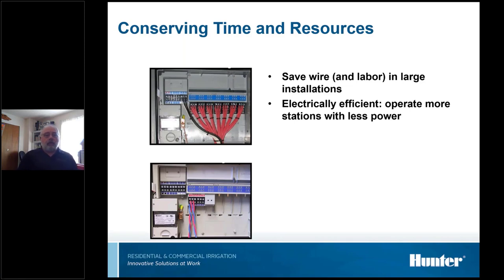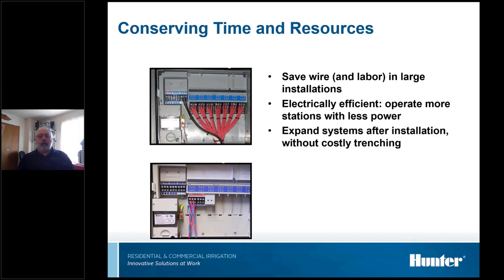One of the things about two-wire systems is they're electrically efficient. I'll explain later why, but with the nature of them, we can run way more stuff at once and only consume the same amount of power. It's really easy to expand systems. We just cut another wire in, or bring another wire to the controller and run off in another direction. It also helps, at least in some cases, with troubleshooting. If everything after a certain point is not working, then you know where to start.